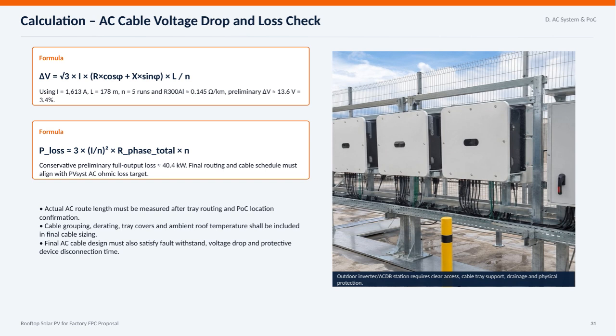Using a current of 1,613 amperes, a cable length of 178 meters, 5 cable runs, and a resistance of approximately 0.145 ohms per kilometer for our 300 aluminum conductor, we get a preliminary voltage drop of about 13.6 volts, which corresponds to 3.4%. Next is the power loss formula, which estimates the loss as 3 times the square of the current divided by the number of runs, times the total phase resistance, times the number of runs. The conservative preliminary full output loss is approximately 40.4 kilowatts.